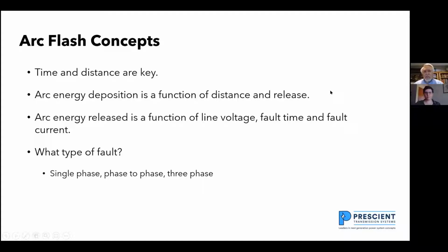So the key concepts we're worried about are time and distance. If I clear faults quickly and I keep dry vegetation far away, I'm not going to ignite fires. The amount of energy I deposit on dry vegetation is a function of distance, and the energy I release is a function of line voltage, fault time, and fault current. Line voltage is important because as line voltage increases, the length of an arc is going to increase because the size of insulators is greater. Then I also want to consider what type of fault I have. Do I have a single phase fault, a phase-to-phase fault, or a three-phase fault?